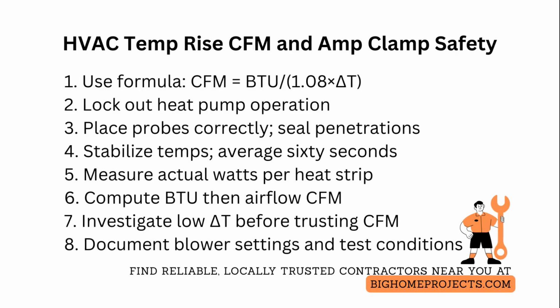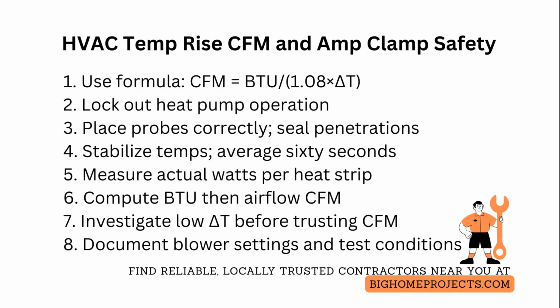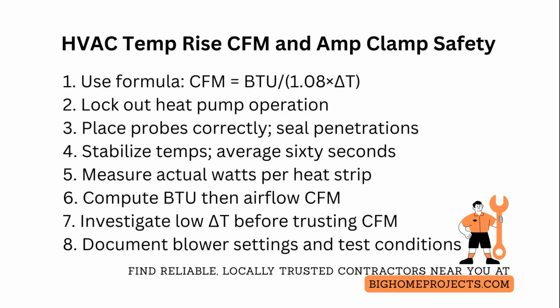Use a true watt reading from a power meter if available. If you must use current and voltage, measure each heat strip leg separately, multiply line voltage by current for each energized strip, and add them to get total watts.